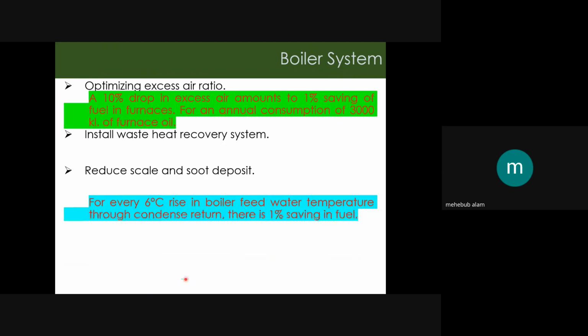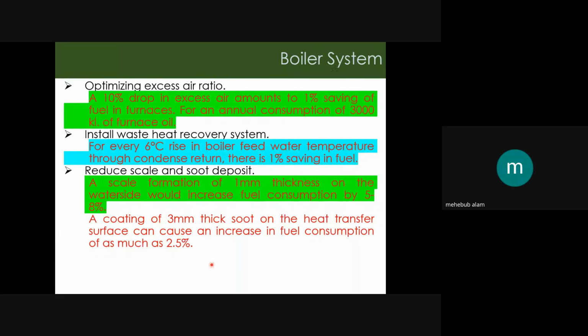Like in boiler system, if we optimize the boiler operation, there is some statistical data, like a 10% drop in excess air will be helpful to save 1% of the fuel in the furnace. And it can have a capacity of an annual consumption of 3,000 liters of furnace oil. And installation of a waste heat recovery system: if we can install a system that can recover the waste heat from the furnace output, then for every 6 degrees centigrade rise in boiler feed water temperature through condense return, there is 1% saving in the fuel.